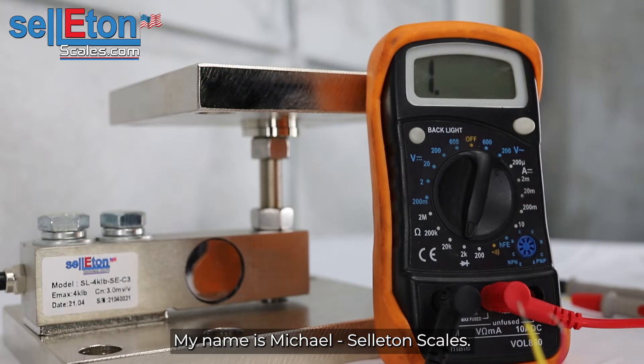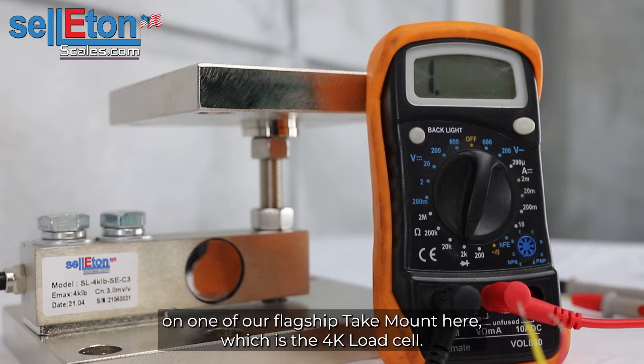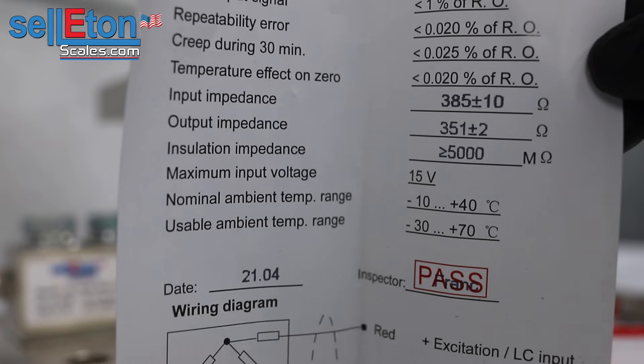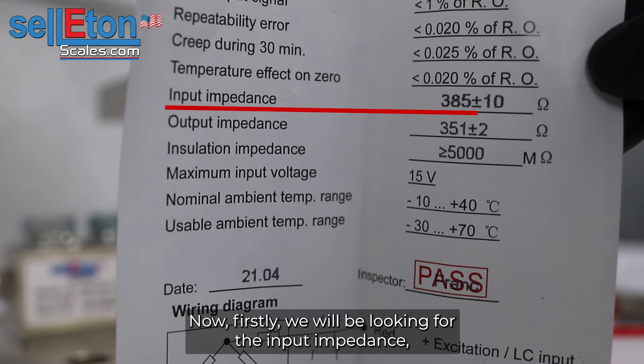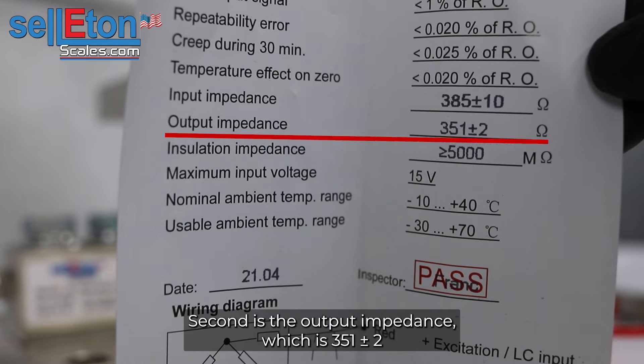Hello everyone, my name is Mike with Selleton Scales. Today we are looking to do an ohms test on one of our flagship tank mounts, which is the 4k load cell, to determine whether it is a good or bad load cell. We'll be looking for the input impedance, which is 385 plus or minus 10, and the output impedance, which is 351 plus or minus 2.